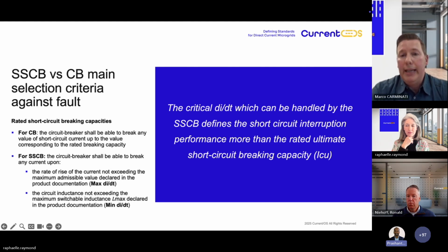So it defines a minimum I squared t, in order to be able to handle the energy, in particular in those solid-state circuit breakers having a metal oxide varistor inside. So as you can see on the right, if we talk about the solid-state circuit breaker, the critical di/dt, which can be handled, defines the short circuit interruption performance more than the traditional rated ultimate short circuit breaking capacity, ICU, that we have with a traditional electromechanical circuit breaker.